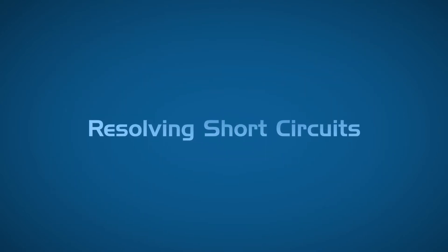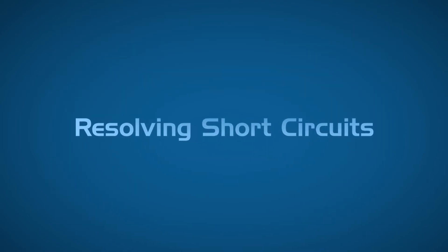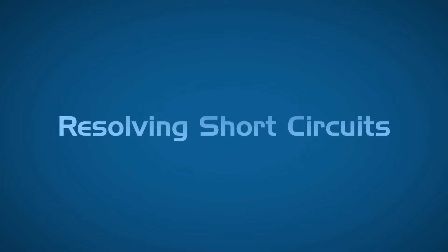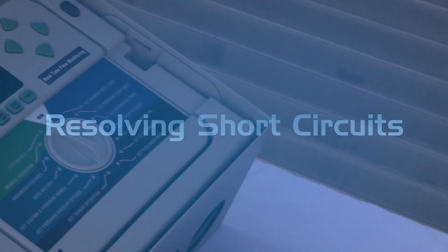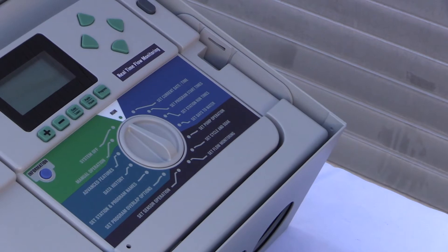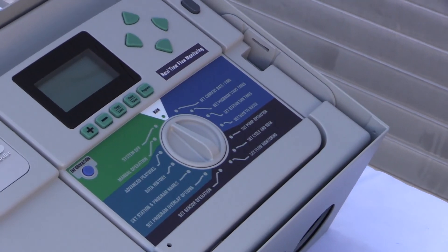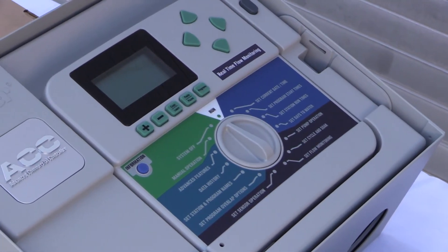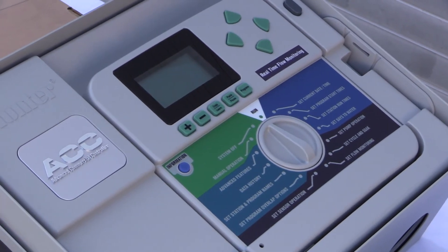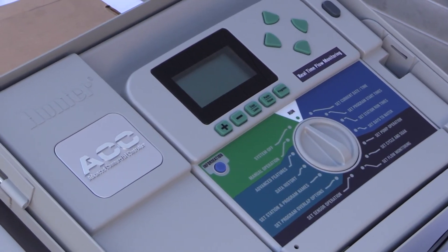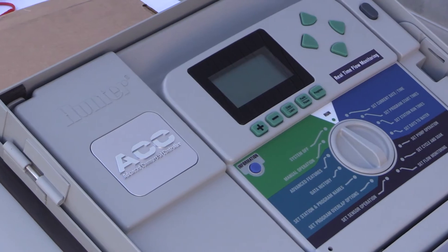Most controllers will display an alarm or otherwise go into short circuit mode when there is a short in the field wiring. When measured at the controller with a clamp meter on the main cable, a short circuit will display a dramatically higher than normal current flow. This can be caused by a bad decoder or unintended crossing of the two wires in the path.